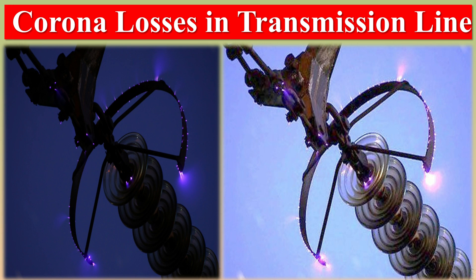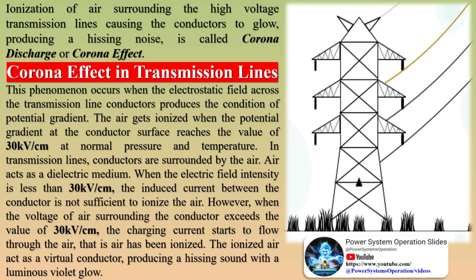Ionization of air surrounding high-voltage transmission lines, causing the conductors to glow and producing a hissing noise, is called corona discharge or corona effect. This phenomenon occurs when the electrostatic field across the transmission line conductors produces the condition of potential gradient. The air gets ionized when the potential gradient at the conductor's surface reaches the value of 30 kV/cm at normal pressure and temperature.